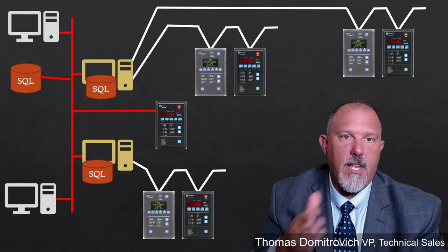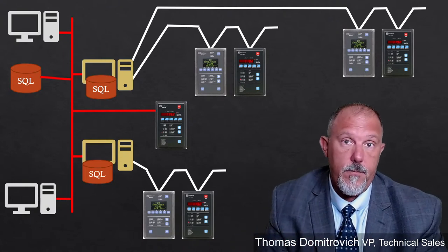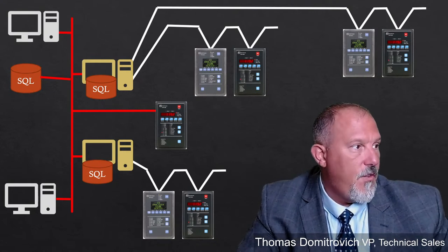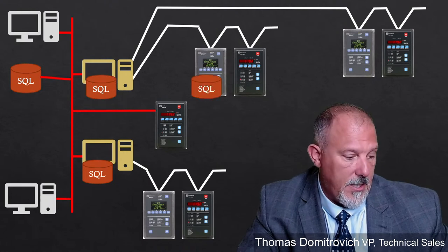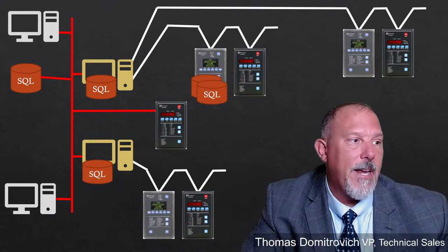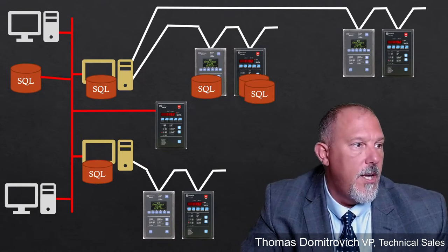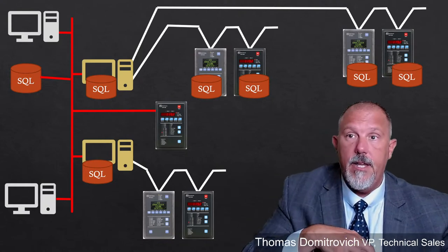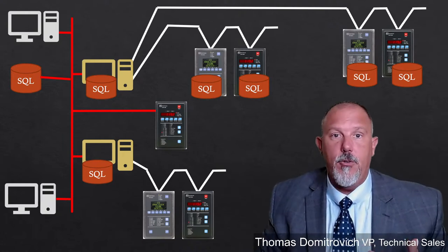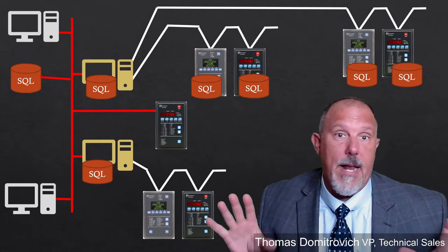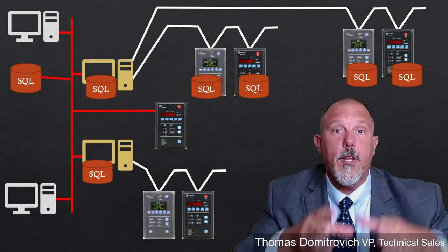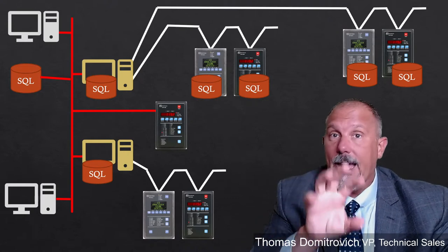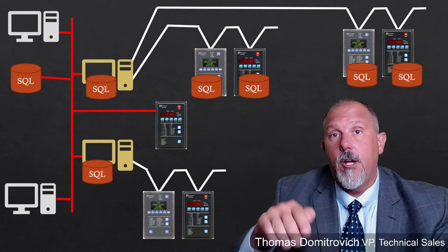Okay, if you're logging, it's better to log locally. In fact, if you could do something like this, the expense would go up, obviously. And I'm just using SQL. It might not be SQL Server. It could be text files. But if you've bought meters and equipment that stored data locally that you could periodically go and grab and upload, now you're even better off, because it doesn't matter what happens: each meter is storing locally and now you can upload information. We do a lot of this with regard to capturing waveforms or doing load demand local.